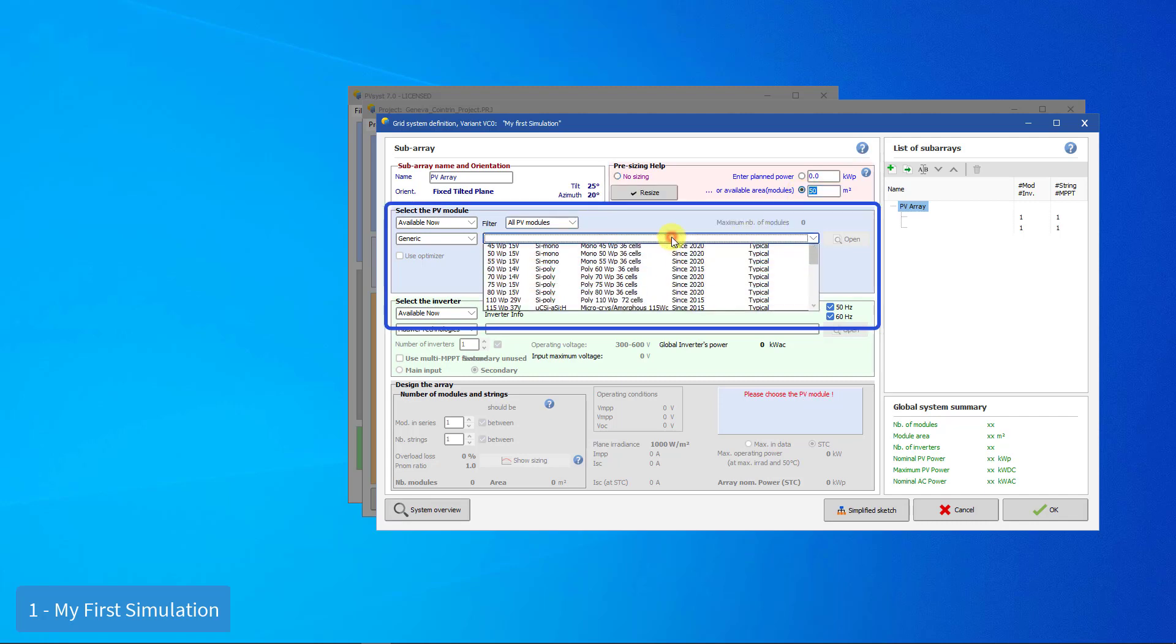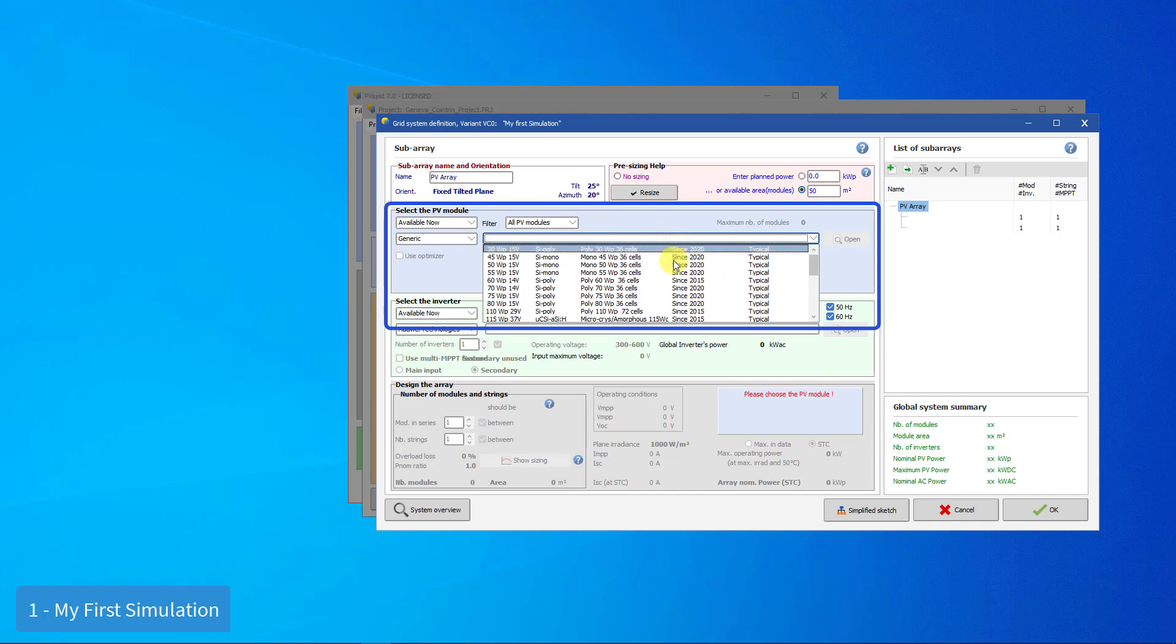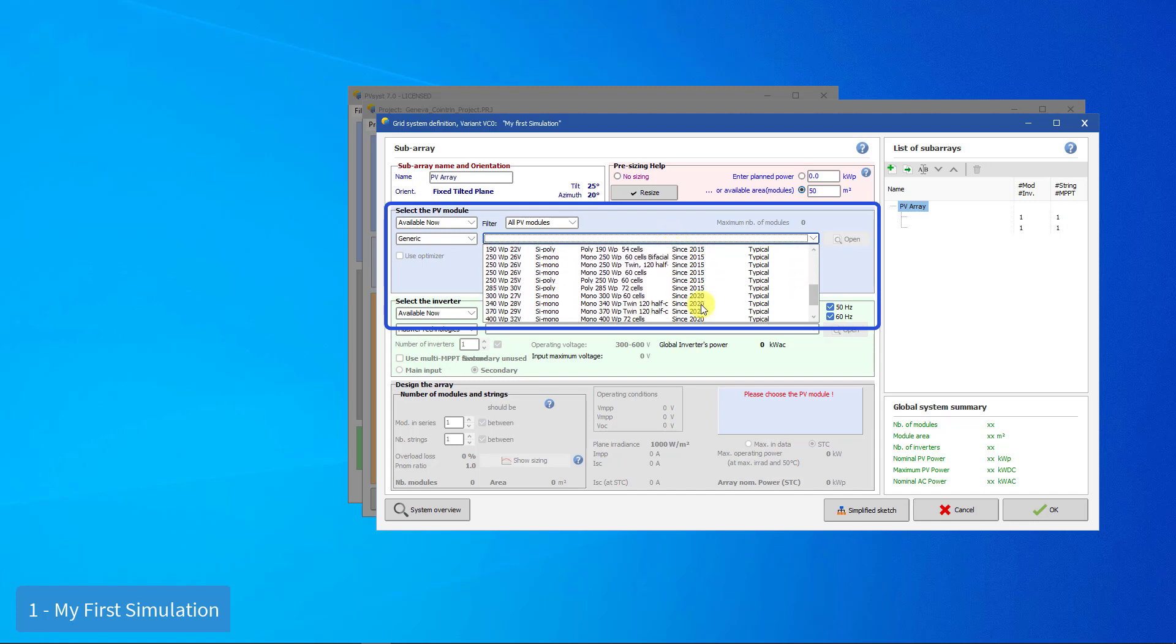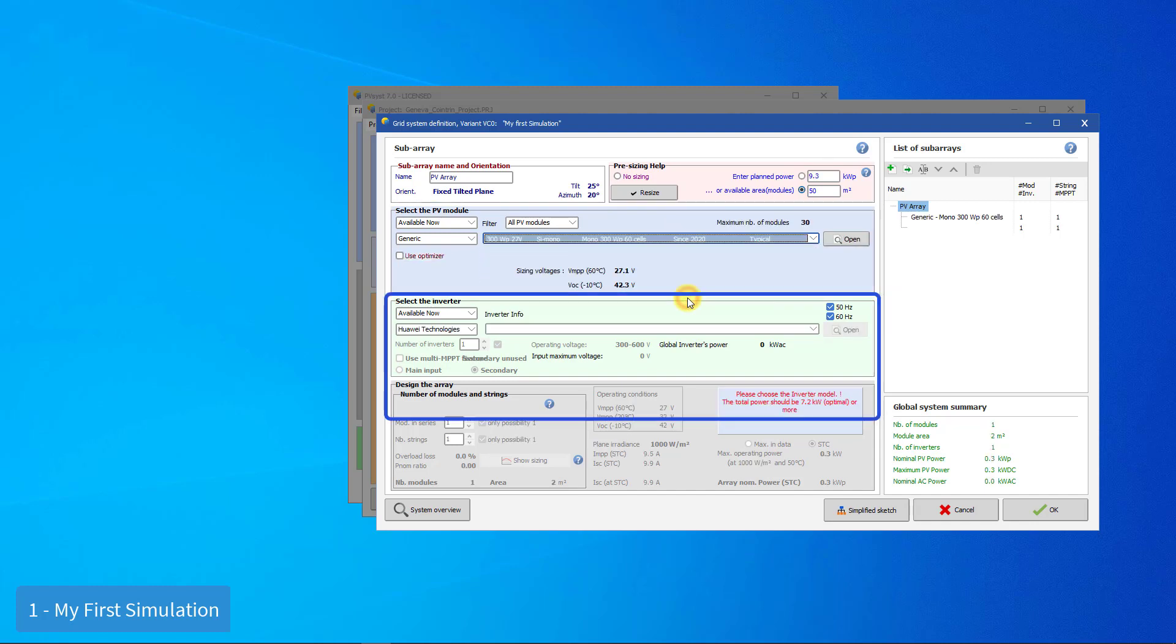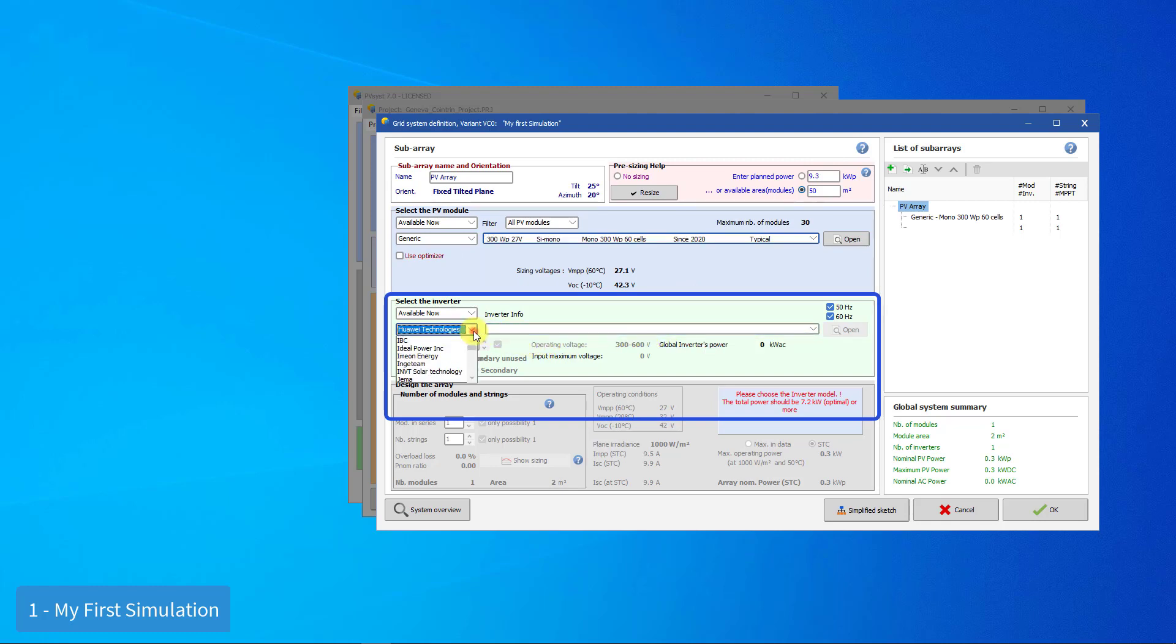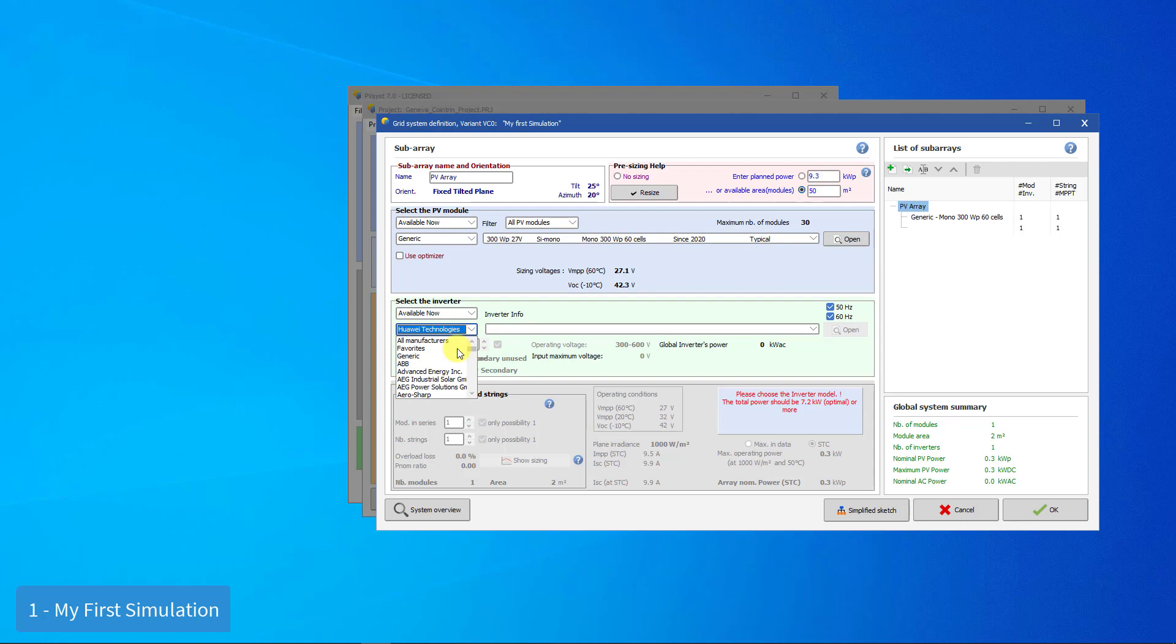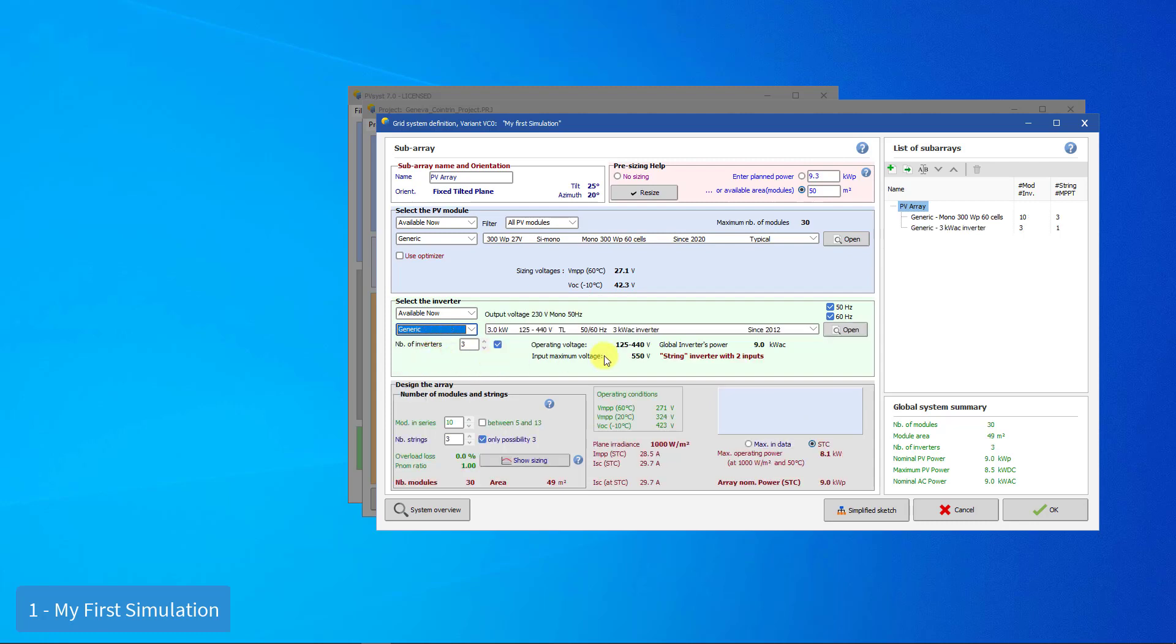You now have to choose a PV module in the database. We will use a generic 300-watt peak panel. We also have to choose an inverter. PVSyst suggests the suited inverter power. We will use a 7.5-kilowatt inverter.